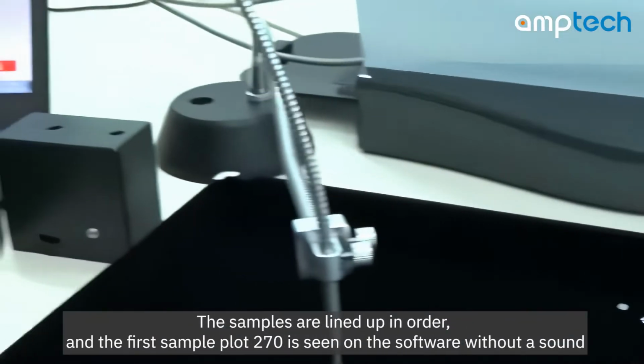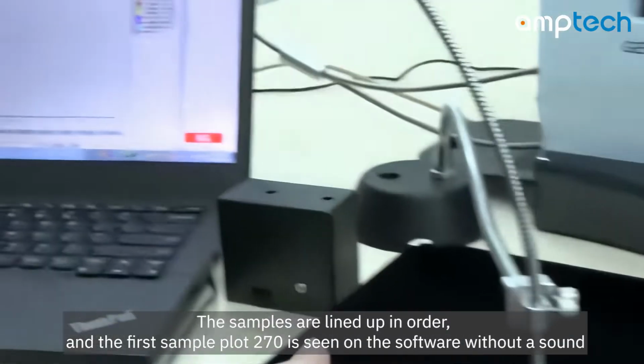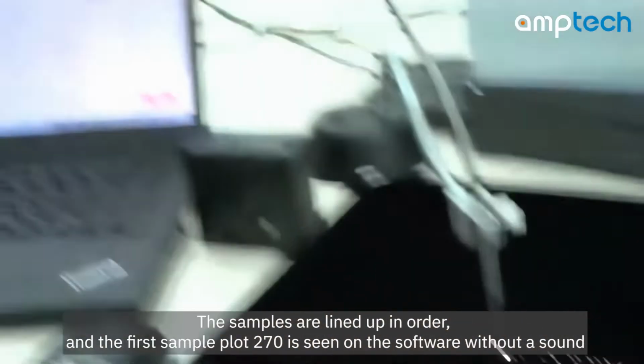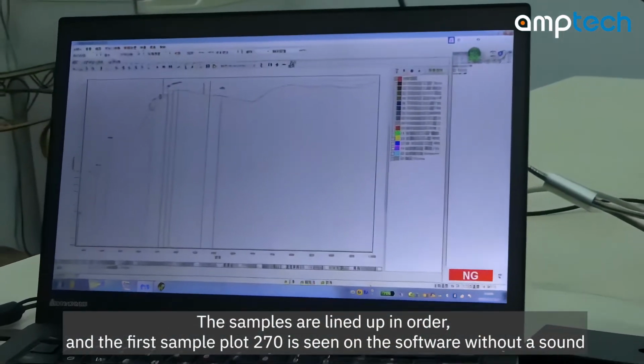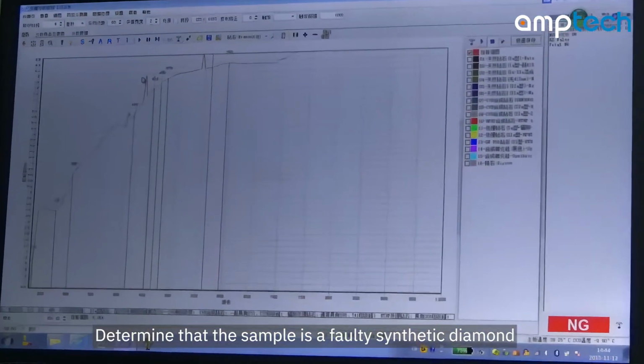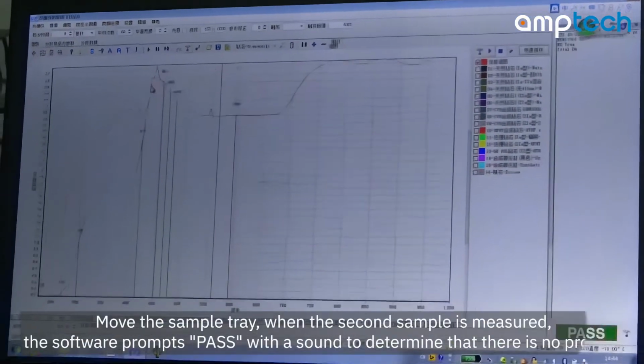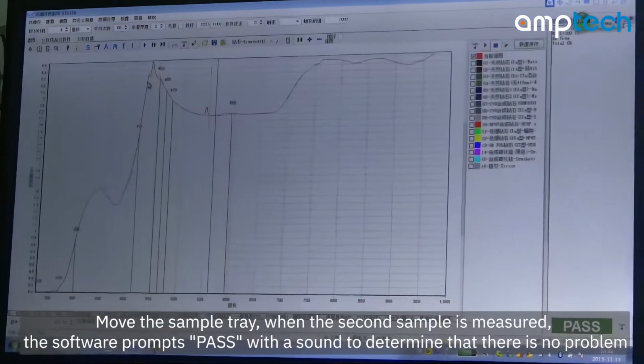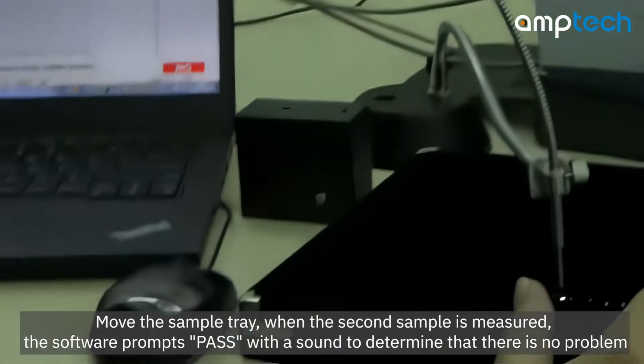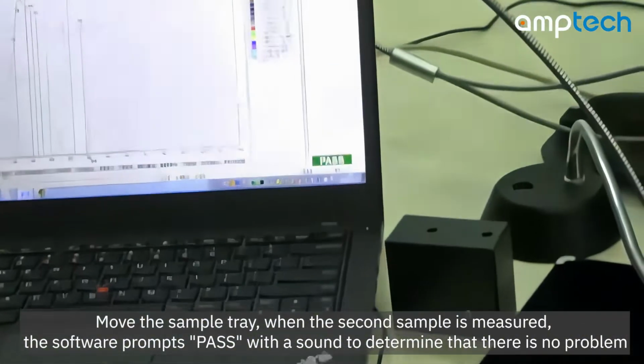The samples are lined up in order, and for the first sample, a plot with a 270 absorption is seen on the software without a sound. Determine that the sample is a faulty synthetic diamond. Move the sample tray. When the second sample is measured, the software prompts pass with a sound to determine that there is no problem.